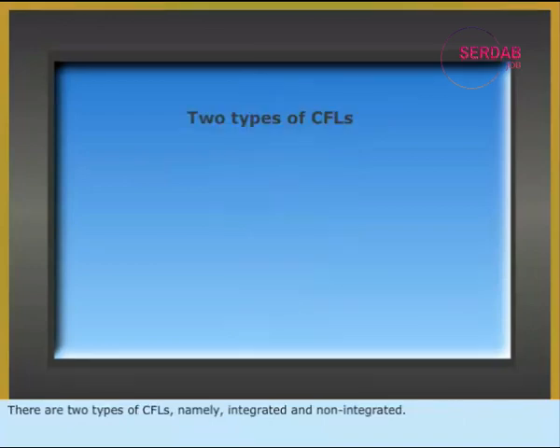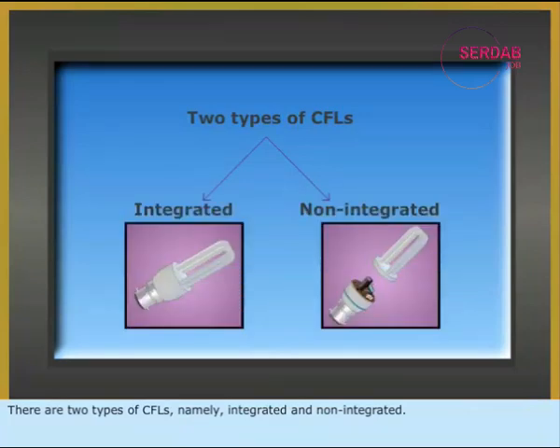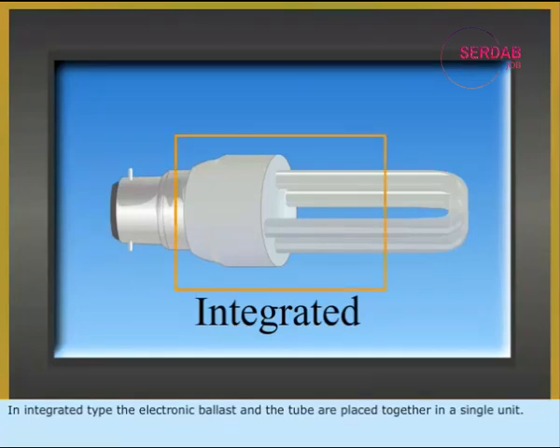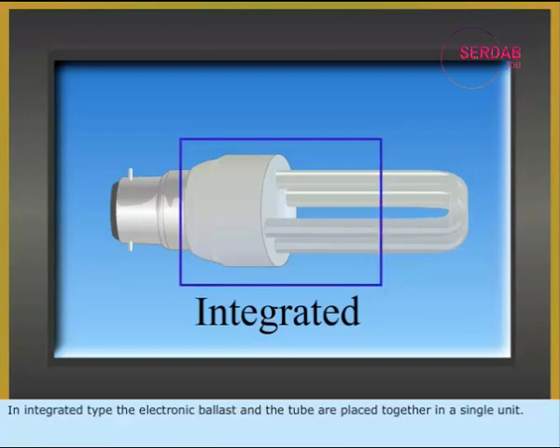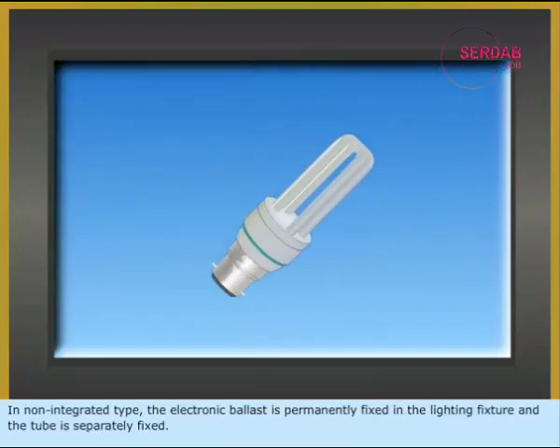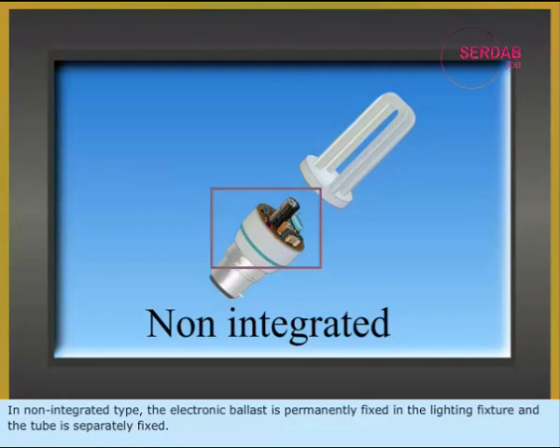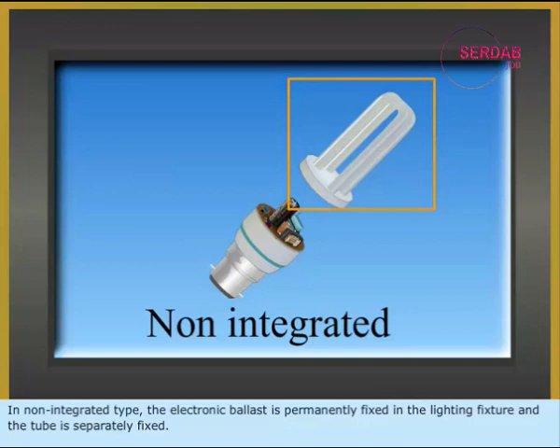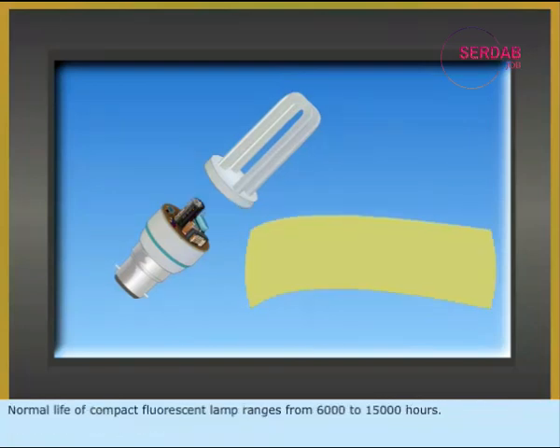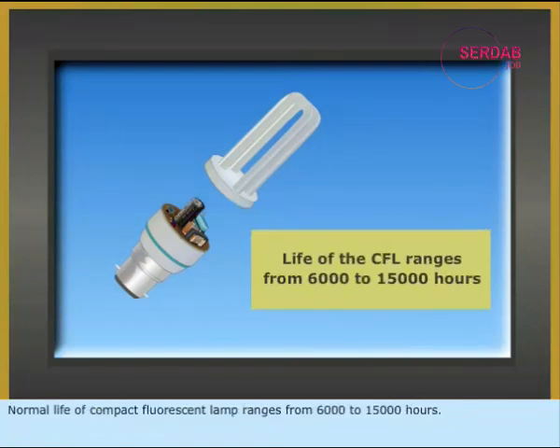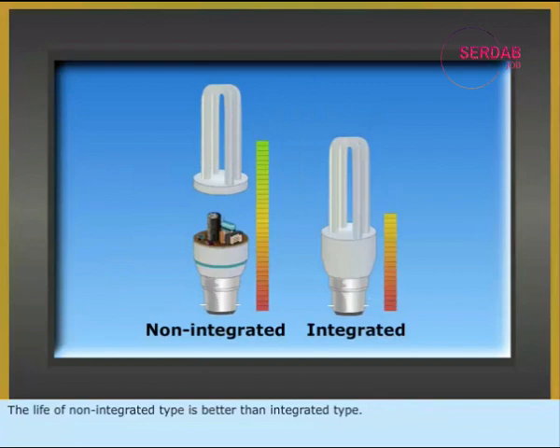There are two types of CFLs, namely integrated and non-integrated. In the integrated type, the electronic ballast and the tube are placed together in a single unit. In the non-integrated type, the electronic ballast is permanently fixed in the lighting fixture and the tube is separately fixed. The normal life of a compact fluorescent lamp ranges from 6,000 to 15,000 hours, and the life of the non-integrated type is better than the integrated type.